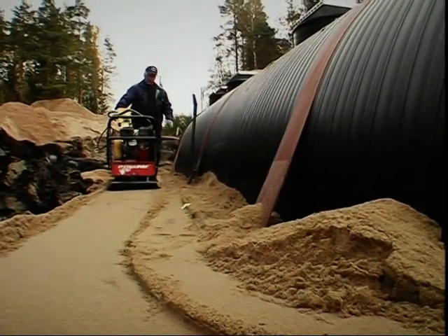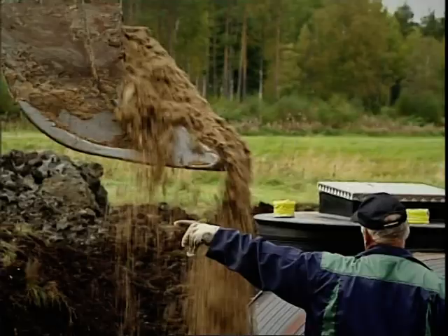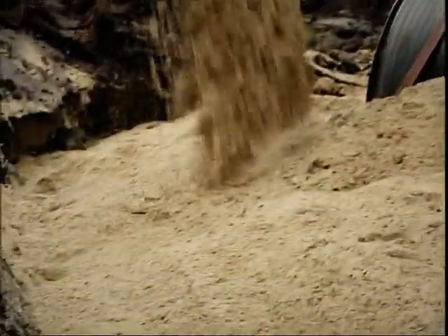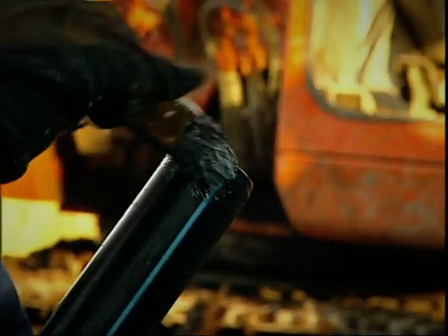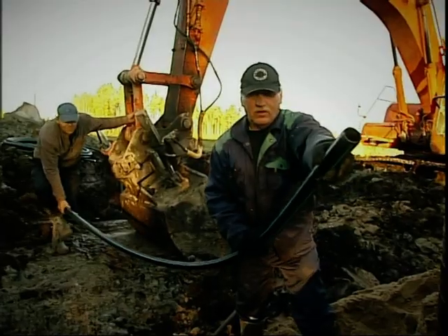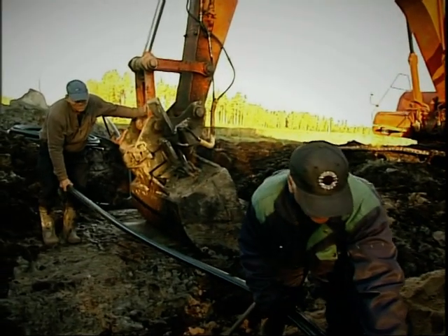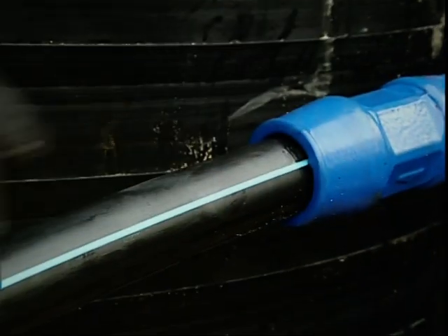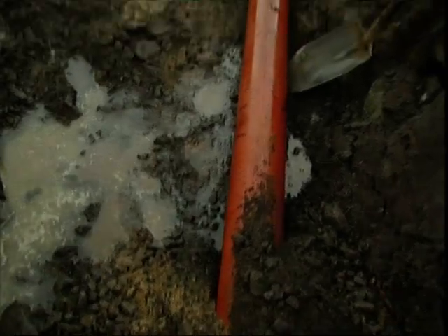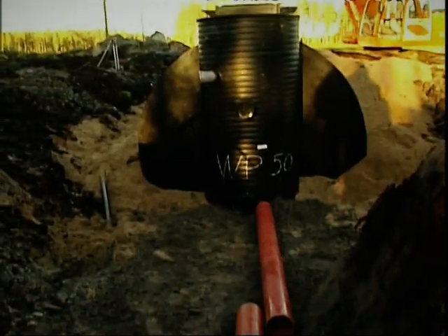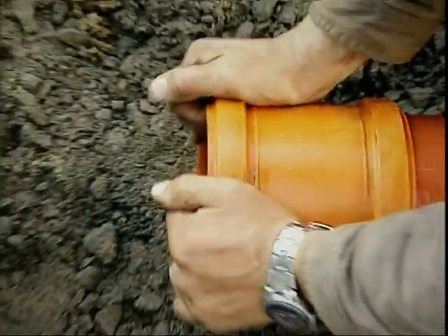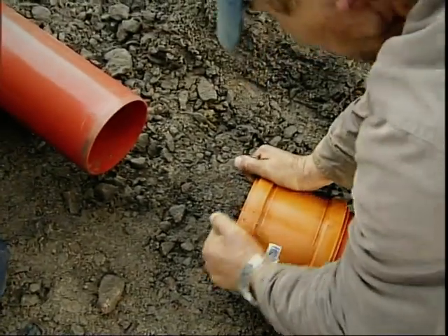Filling material should not be dropped on the plant. Backfilling should be made equally over the whole width and length of the trench. The effluent outfall must be made according to local authority regulations. To prevent freezing, effluent connections, overflow and incoming sewage pipes should be provided with frost protection. The inlet pipe can be made either as a non-pressure or a pressure line.